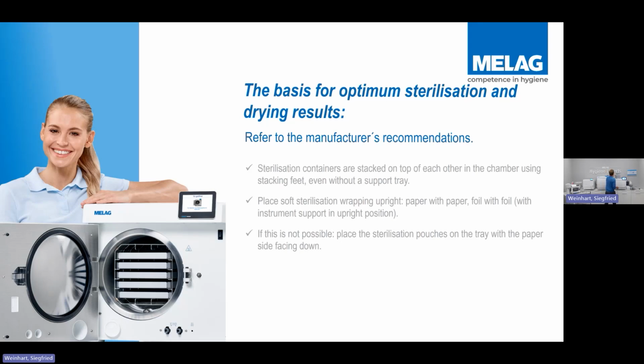With your paper, if you have what we call a toast rack for your sterilizer, I see quite a few of them out there. I don't see many practices using them, but this is where your pouched instruments theoretically will go like this. The way you would put your pouch in there would be either clear view to clear view or paper to paper. So you're putting them the same way from each other. If you don't have a rack that sits in your pouches like this, then perforated tray. For a MELAG unit, you are placing the paper side down for MELAG units.